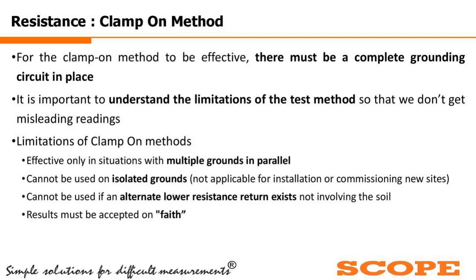So in a normal system with some limitations, it cannot be used if an alternate lower resistance return exists not involving the soil. This measurement cannot understand whether the system is picking up the leakage current flowing through the ground path, or flowing through any other parallel or low resistance path available in parallel with the grounding system. It cannot understand. So ultimately the result must be accepted on faith. So this is the very basic thing.